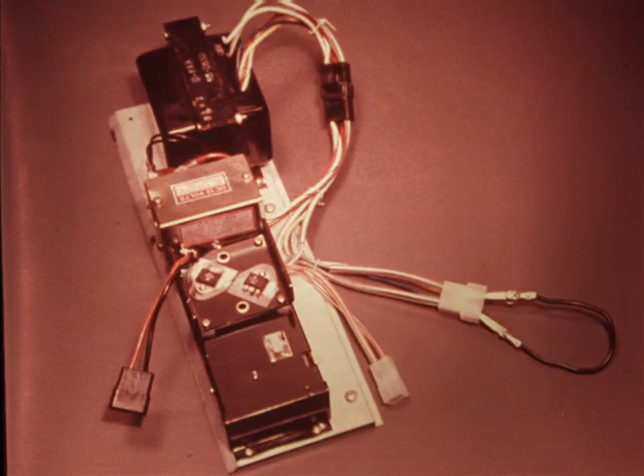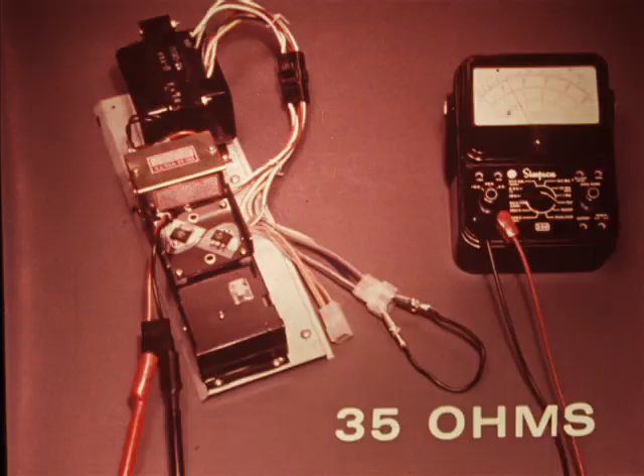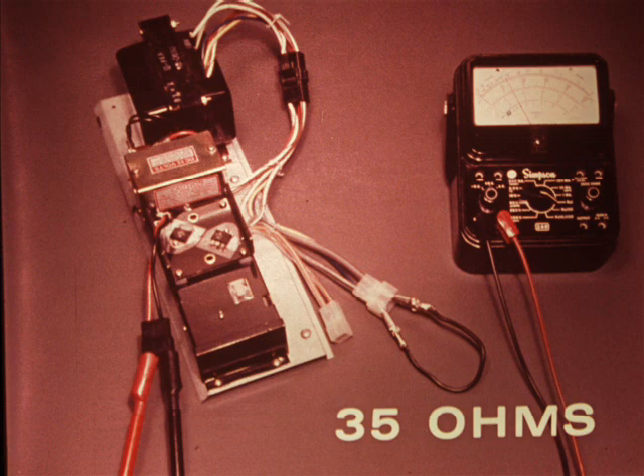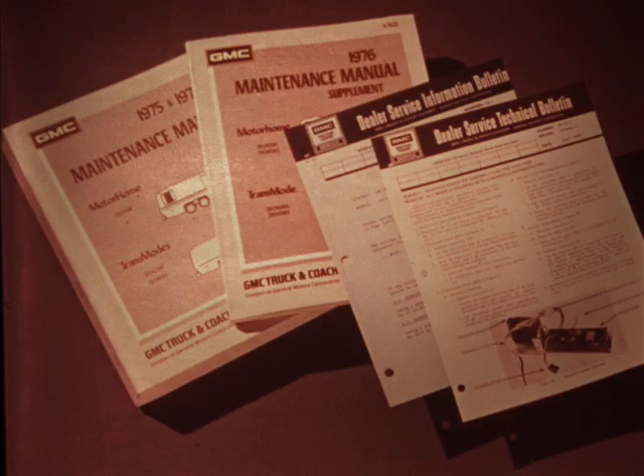Test the inverter with the transformer connector hooked up and a jumper wire across the terminals of the gray thermostat wires. Measure the resistance between the 12-volt leads to the inverter. It should be about 35 ohms, but can be between 4 ohms and 60 ohms, and the inverter still good. The test procedures we've just summarized for the refrigerator are detailed in Bulletin 76 IM1 and 76 TM2, and in the maintenance manual. One final point.